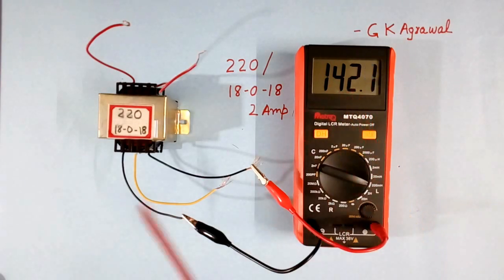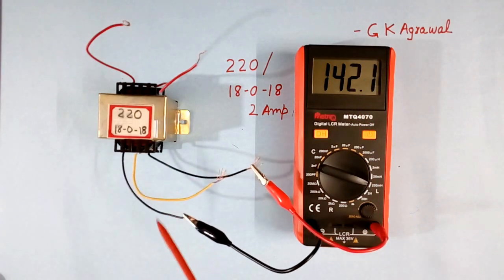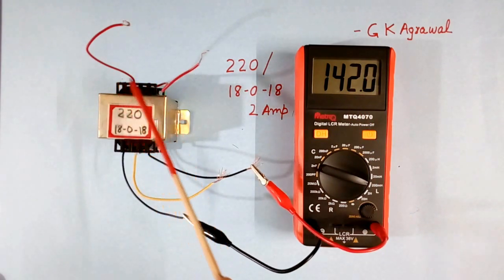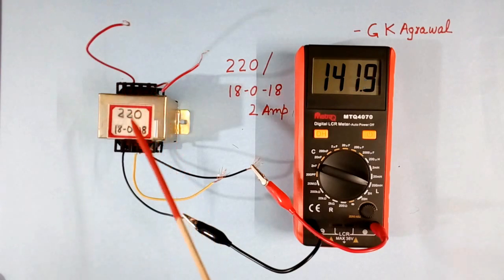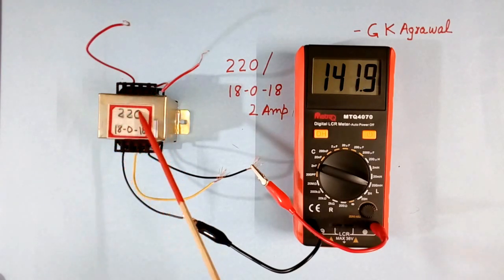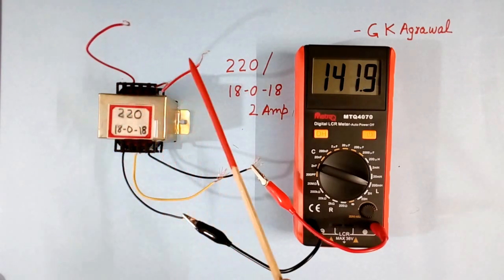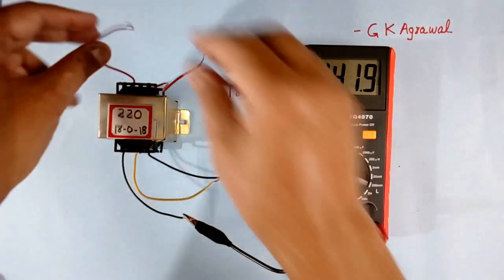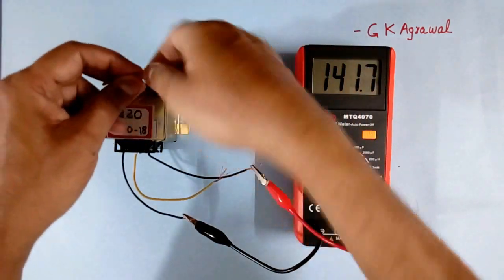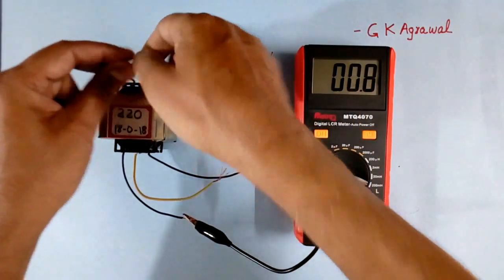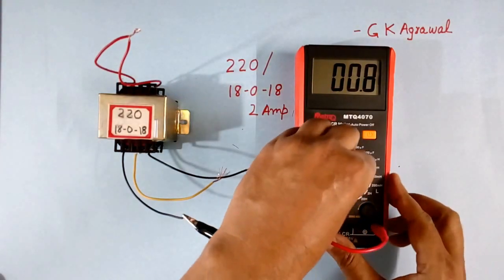But if we use it like this, very high voltage will come here. So we should never use a transformer as an inductor like this. We should always short the primary wire. So I will short again.